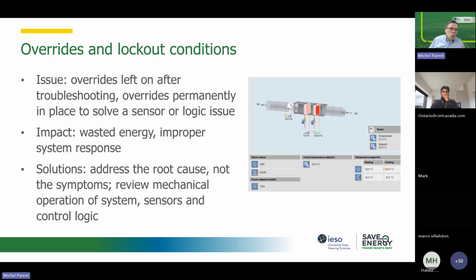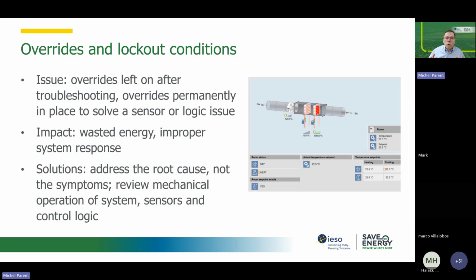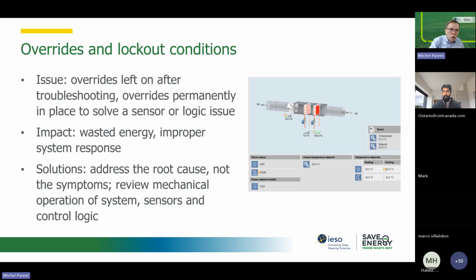Another sign is to look for overrides. You see on that screen, there are 2 overrides on critical components. The override is on the damper for the VAV box and on the reheat coil for the VAV box. And those 2 settings are incompatible right now. But before you remove them, identify all of the overrides, and then your operating team needs to say why we have this override. We need to resolve the root cause before we remove the override.